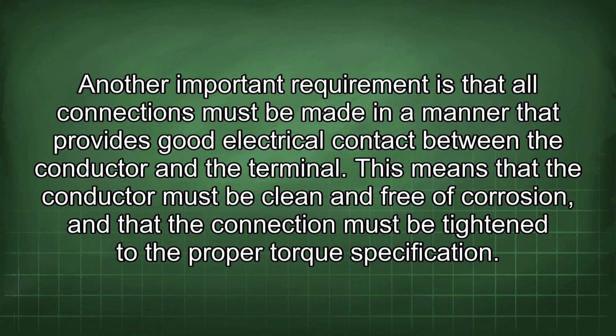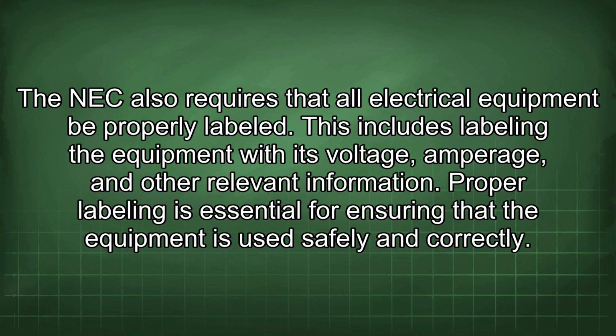Another important requirement is that all connections must be made in a manner that provides good electrical contact between the conductor and the terminal. This means that the conductor must be clean and free of corrosion, and that the connection must be tightened to the proper torque specification. The NEC also requires that all electrical equipment be properly labeled. This includes labeling the equipment with its voltage, amperage, and other relevant information. Proper labeling is essential for ensuring that the equipment is used safely and correctly.